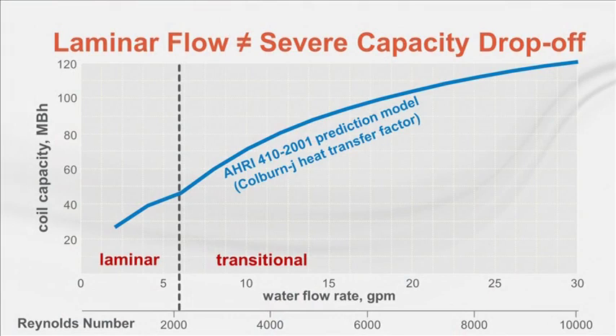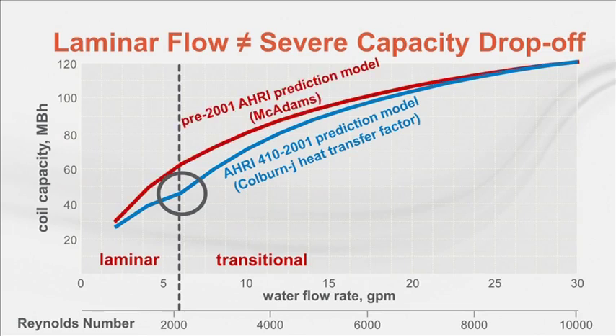While there is a reduction in performance as flow turbulence moves from transitional to laminar, it is by no means as severe as the chart seems to suggest. A chart plotting coil capacity versus water flow rate shows a slight dip in capacity in the laminar region using the 2001 AHRI model — really not an issue. The obsolete pre-2001 AHRI model overestimated capacity, which caused the unwarranted fear of laminar flow. Laminar flow does not cause a severe drop-off in capacity, and the current AHRI prediction methods allow coils to be rated accurately well into the laminar and transitional flow regions.